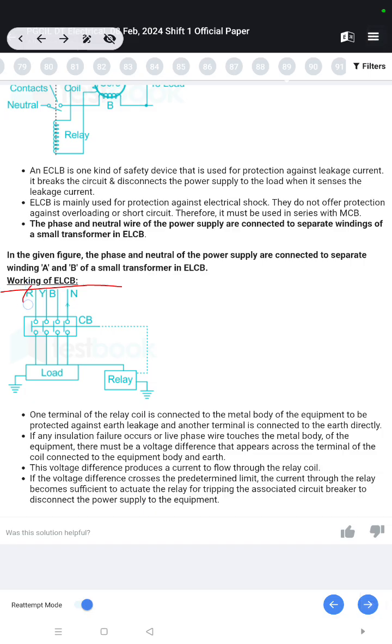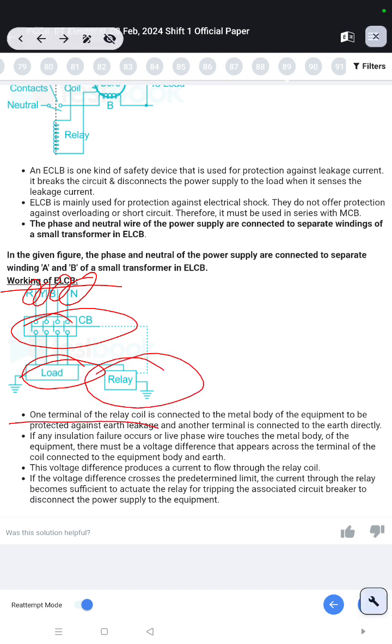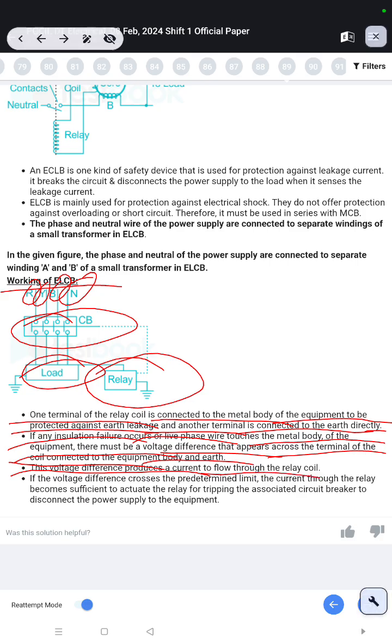R, Y, B, neutral, circuit breaker, load, relay. One terminal of the relay coil is connected to the metal body of the equipment to be protected against earth leakage, and the other terminal is connected to the earth directly. If any insulation failure occurs or a live phase wire touches the metal body of the equipment, there must be a voltage difference that appears across the terminals of the coil connected to the equipment body and earth. This voltage difference produces a current to flow through the relay coil. If the voltage difference crosses the predetermined limit, the current through the relay becomes sufficient to actuate the relay for tripping the associated circuit breaker to disconnect the power supply to the equipment.